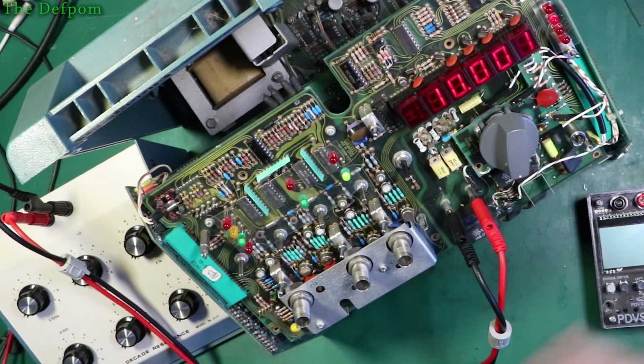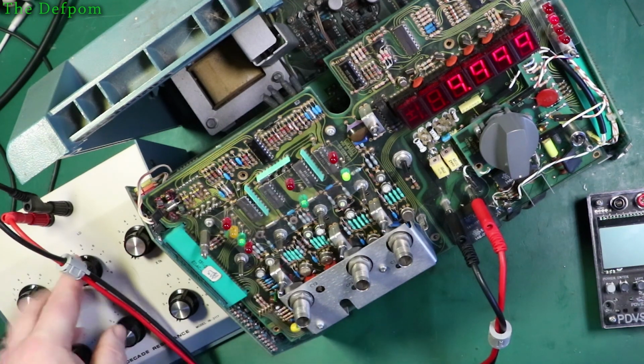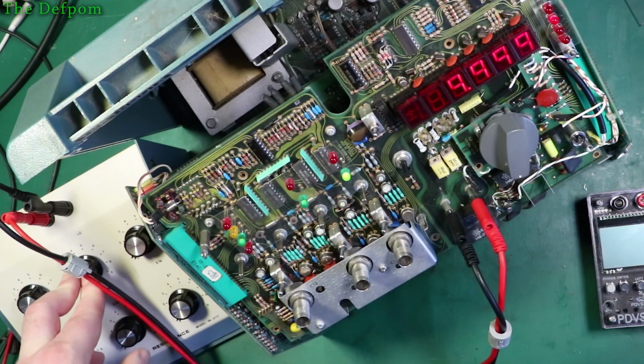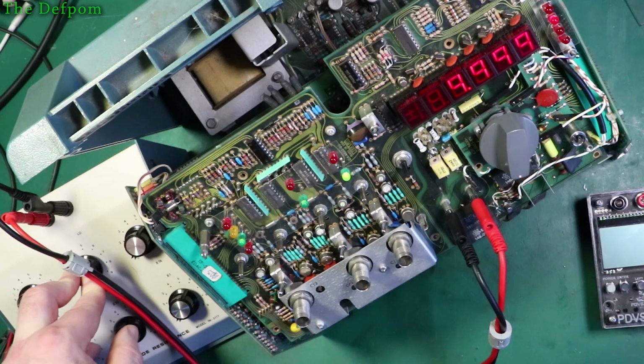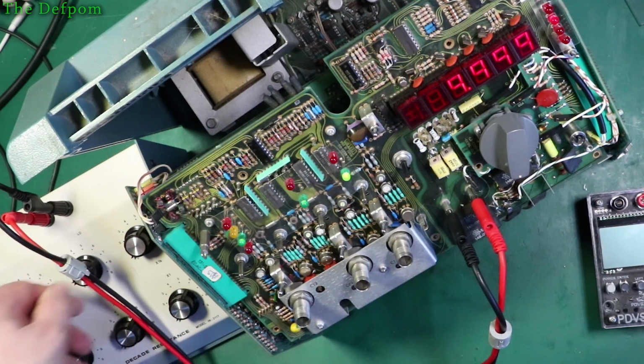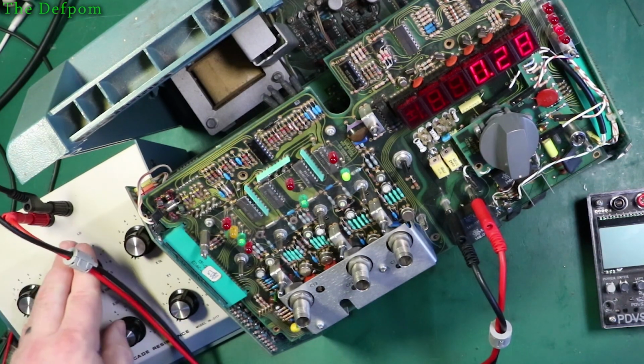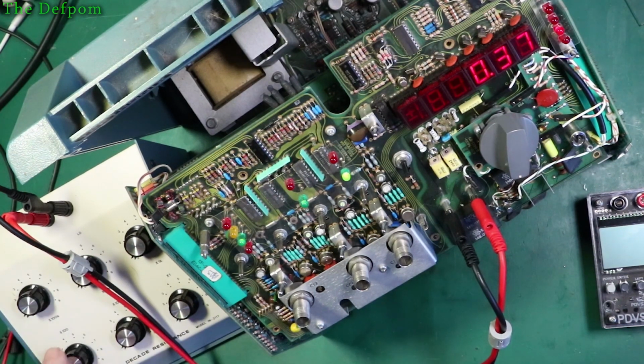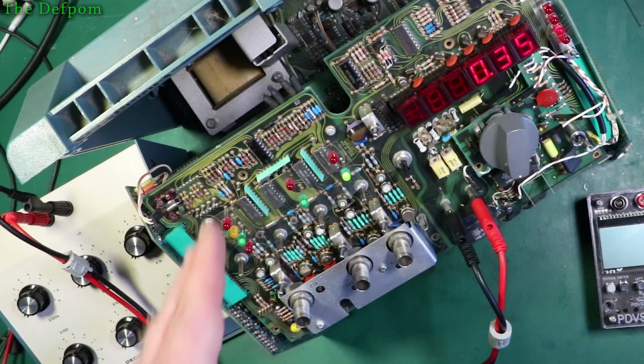10K, it's a bit of a balance. So your calibration point is 10K, that's where you calibrate it, and that is calibrated correctly right now. This is what this thing actually is. So the 10K calibration is correct, the bottom end calibration is correct. Again, the bit in the middle humps up a little bit and is slightly out.